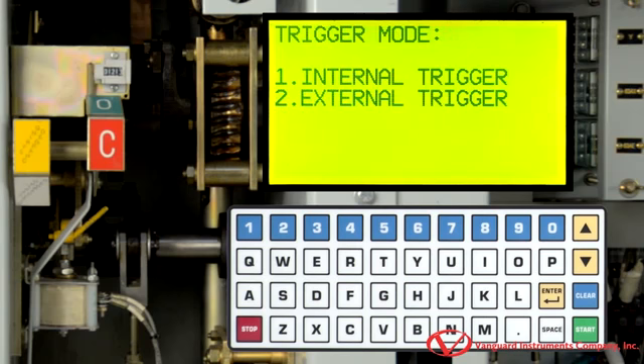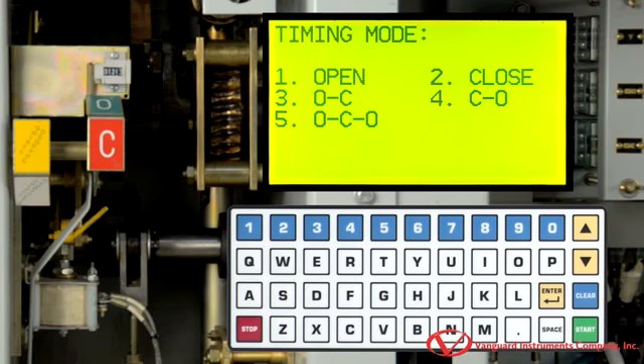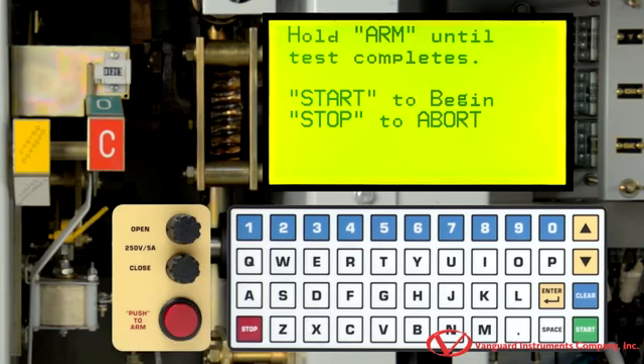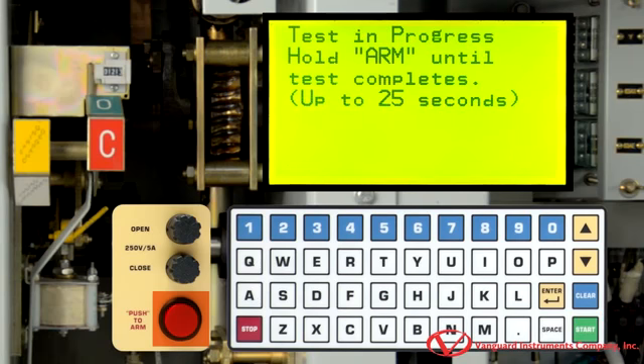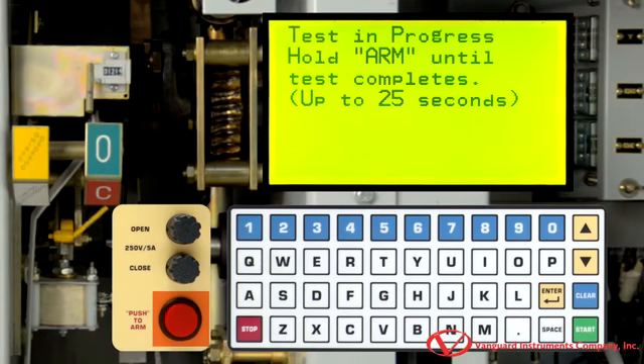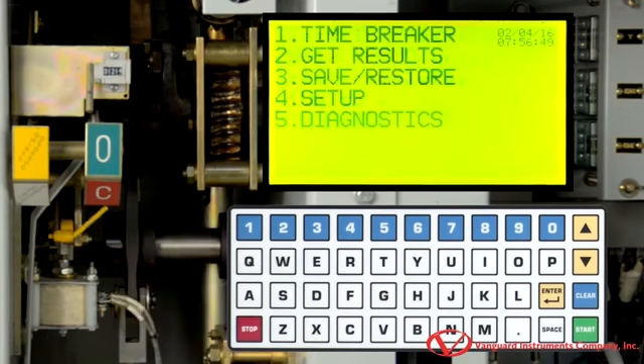Now we will select the trigger mode by pressing 1 for internal trigger. On this screen, we will select the type of test to be performed. In this case, we will press 1 to select an open test. Now, hold down the arm switch and then press the start key to start performing the test. Continue holding down the arm switch until testing is complete. Once testing is finished, we will be returned to the main menu.